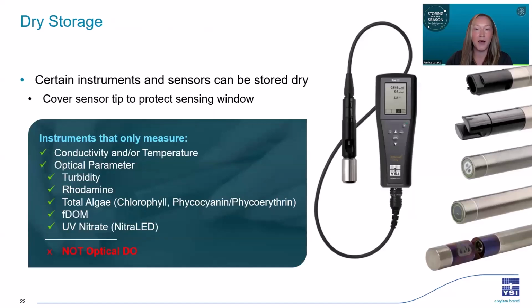If you have an instrument like the ProSwap or the Pro 30 that only measures conductivity, temperature, or an optical parameter like turbidity, rhodamine, chlorophyll, dissolved organic matter, or UV nitrate, you can go ahead and store it dry. Just cover the sensor tip to protect the glass or sapphire sensing window. You can use a shipping cap or a sensor guard to cover the tip. I always recommend keeping those little shipping caps for the sensors when you get them. They come in handy for stuff like this. And I do want to note that this does not apply to the optical DO. The optical DO needs to be stored wet, so keep that in mind.